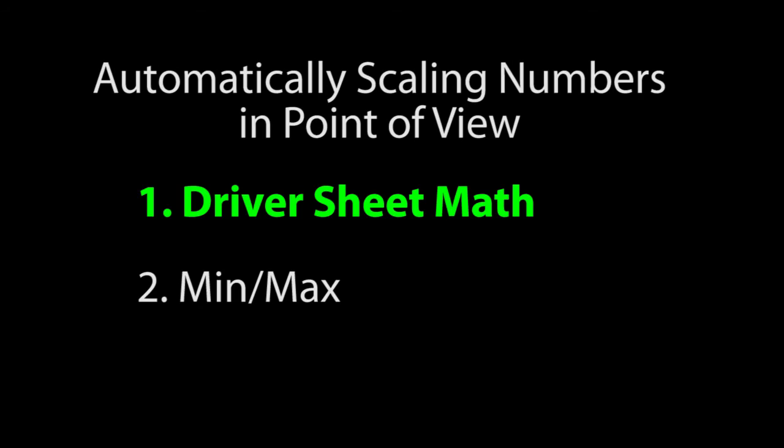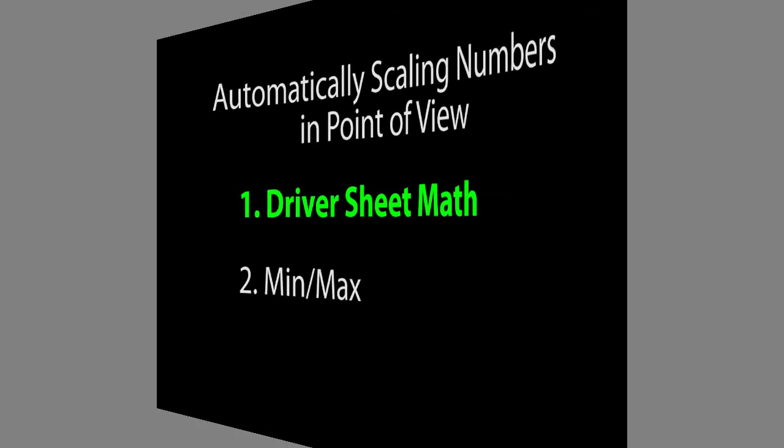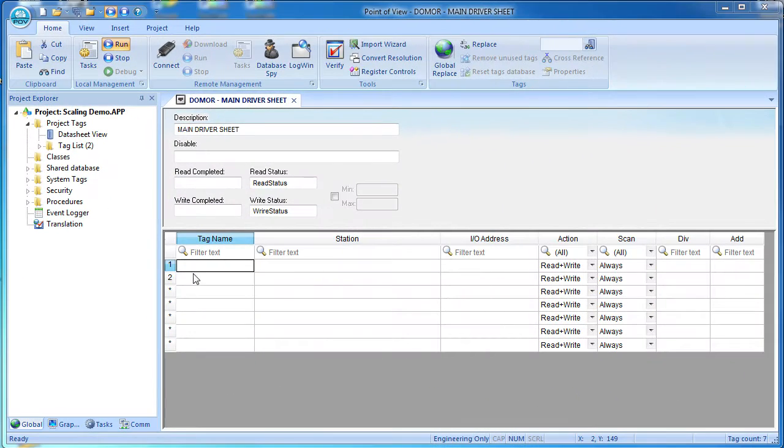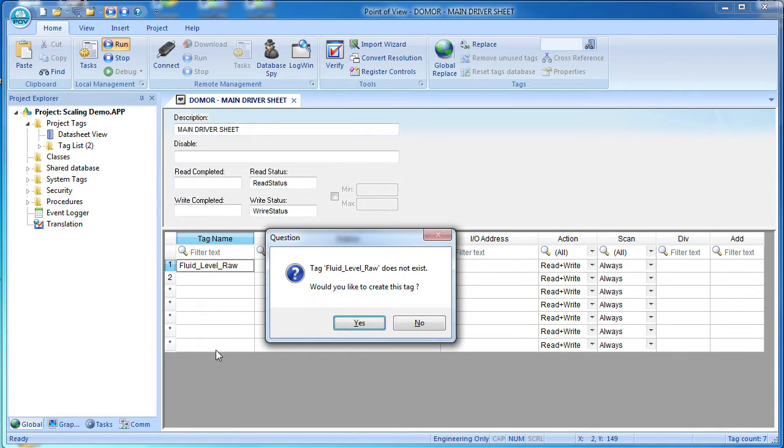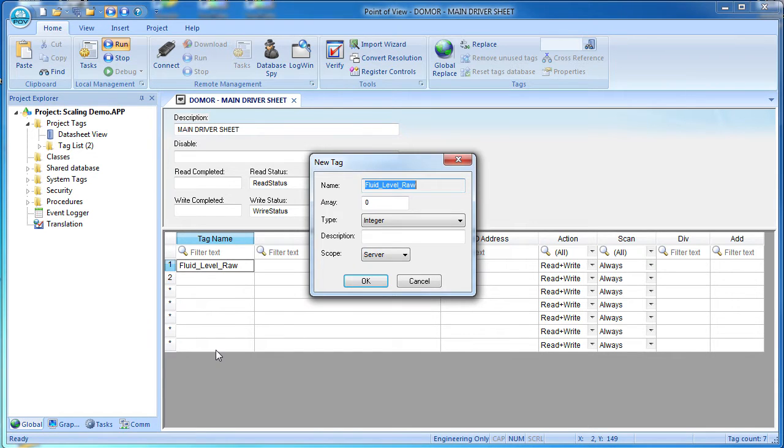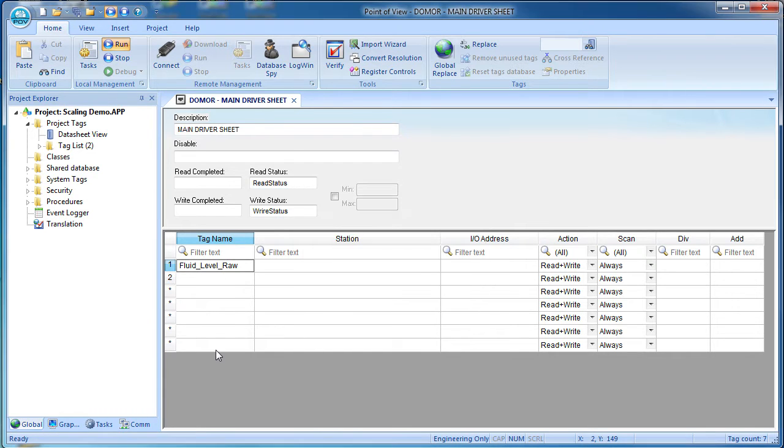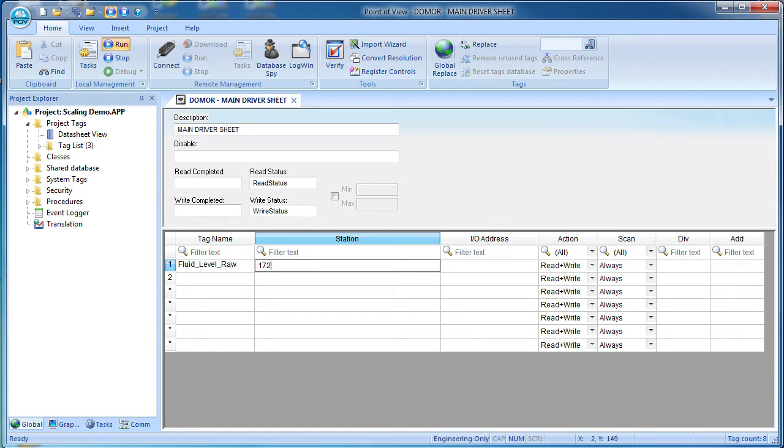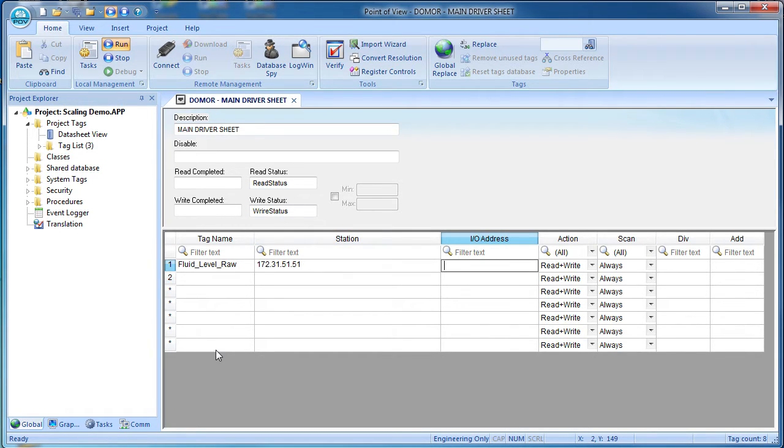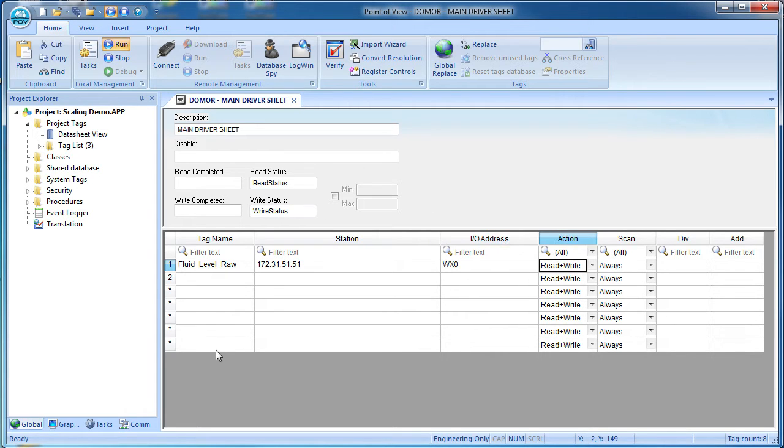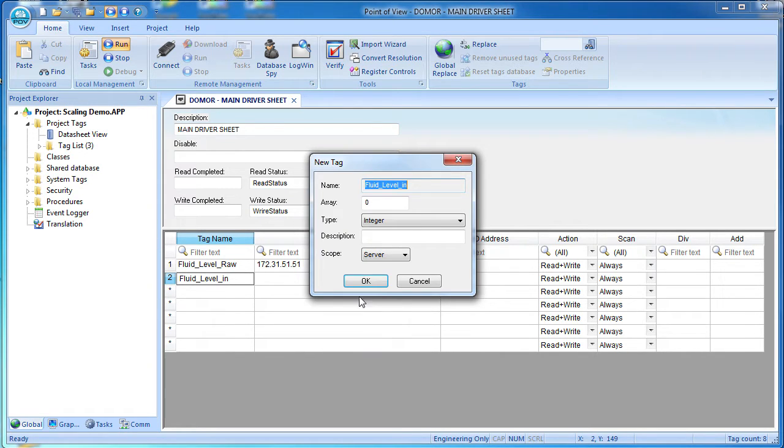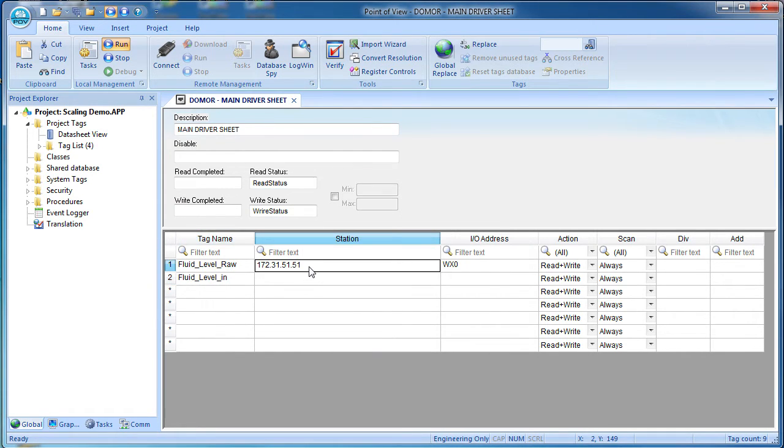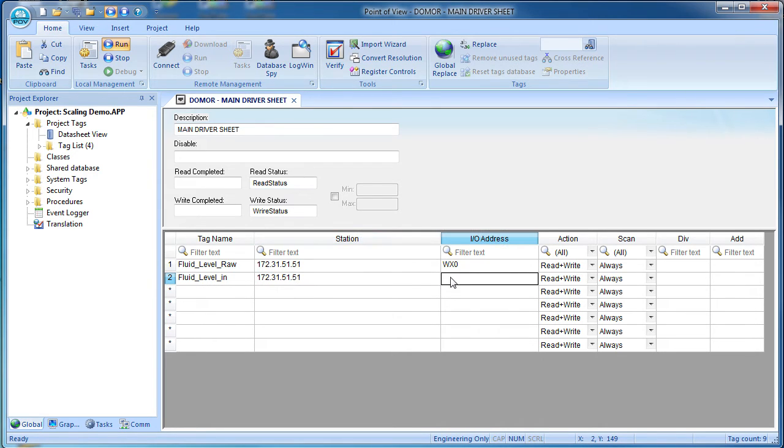First, we'll use the driver sheet math method. Let's create a tag to show the Do-more raw input – we'll call that fluid level raw – and yes we want to create this as an integer tag. The Do-more is at this IP address – we don't need a CSV file here because we are not using any user defined memory – and this is the name of the memory location on the Do-more. Then we'll want the Do-more's converted value in inches – yes we want to create this tag but as a real. Same IP – and this is its name down on the Do-more.